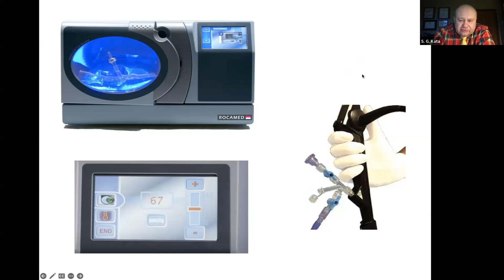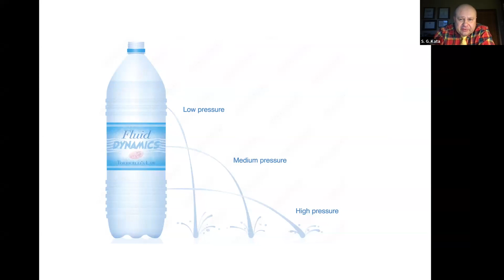Still, the way I'm using is a simple way. I'll just withdraw the ureteroscope from the patient and observe the flow of irrigation fluid, saying most likely it's too high, it's okay, or it's too low. And also after insertion of every instrument, after insertion of a laser or a basket, I'm checking flow from the ureteroscope. It's also quite important because very often you don't have any flow, and the person responsible for putting pressure on the pump is saying, yes, pressure is very high, but at the end, you can see just drops coming from the tip of the ureteroscope.